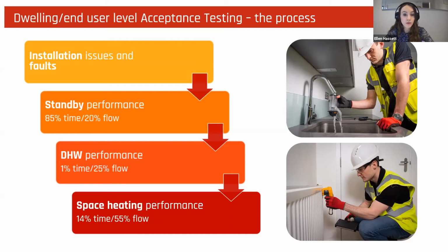And we'll look at standby performance, which involves checking heat meter data to see real-time performance. Hot water performance, which includes checking how long residents need to wait for hot water. Space heating performance, such as checking the commissioning of the heating circuits, whether they're radiators or underfloor heating, and ensuring that the heat output required for the room can be achieved. So the correct commissioning of each mode of operation is essential to network performance, as each mode takes up a large proportion of the total flow or time in any given year, as is shown with the percentages.